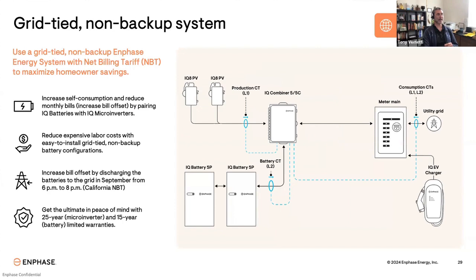Actually, mention one more thing. I'm just going to go back to the grid-tied system, important little detail here, which simplifies the installation. As you can note from this diagram, there's no system controller. As I mentioned a couple of times, that's only needed for backup power. So since this is a grid-tied battery with no backup power, the battery can actually be connected to the IQ combiner if there's sufficient space in there. So say if somebody has 2 branch circuits for PV, they can use the other 2 circuits for batteries in that combiner. And then that means there's only one connection, one breaker that's going to be used in the main panel of that homeowner for connecting the IQ combiner. So if there's limited space in that service panel, this is kind of a nice little feature. Also simplifies the installation.